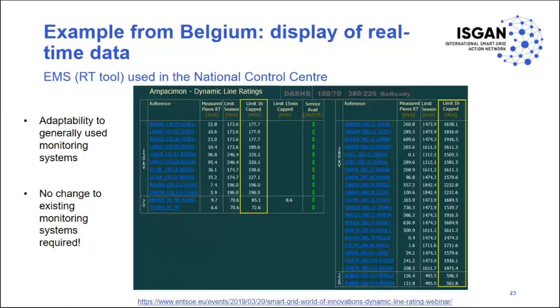Yes, this is a screen capture of Elia's National Control Center energy management tool. So we can see on this screenshot, firstly, very kindly, they put our name at the top left of the screen. So our name is there because they use our data that are mapped into their EMS SCADA.